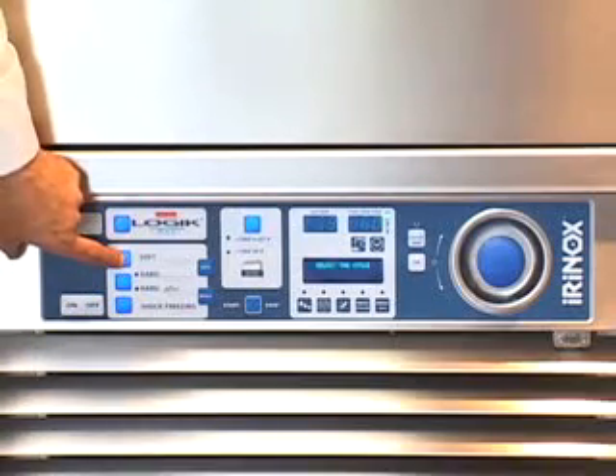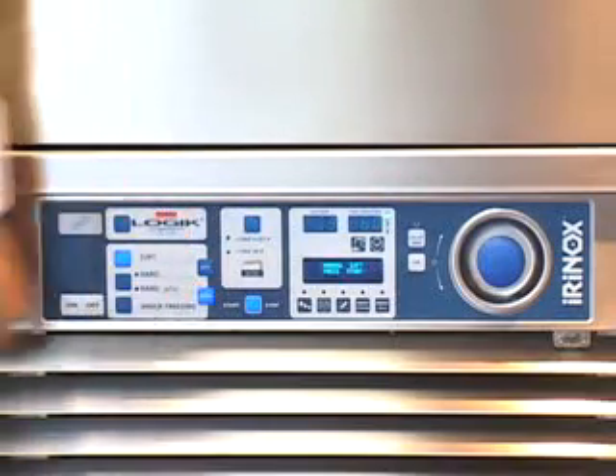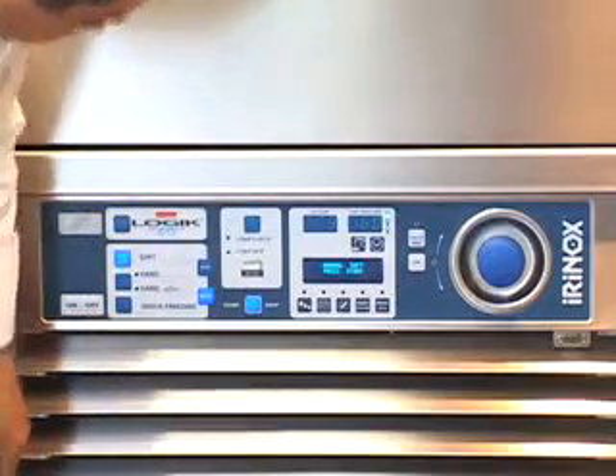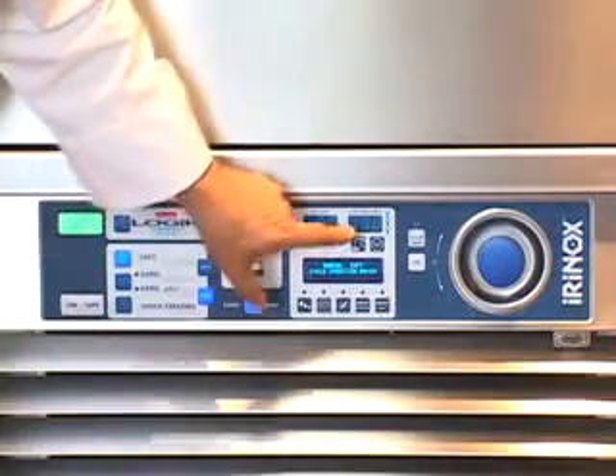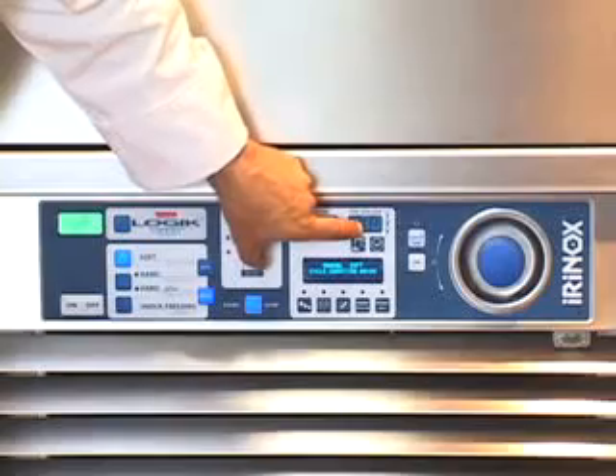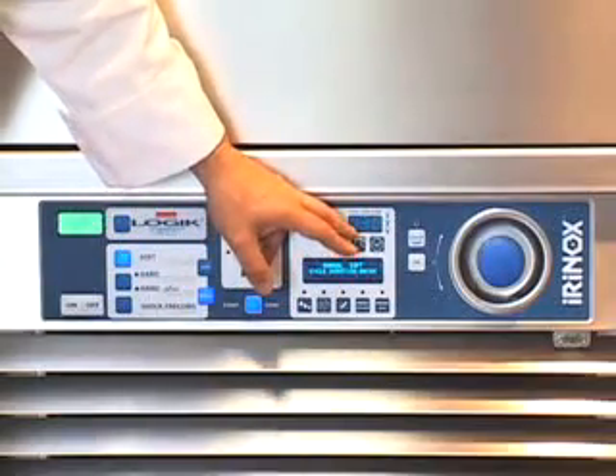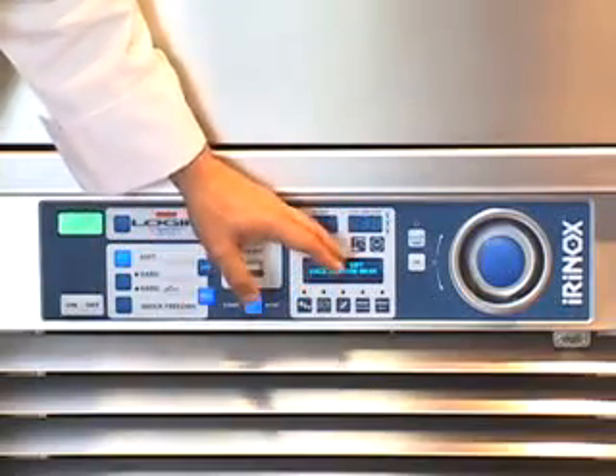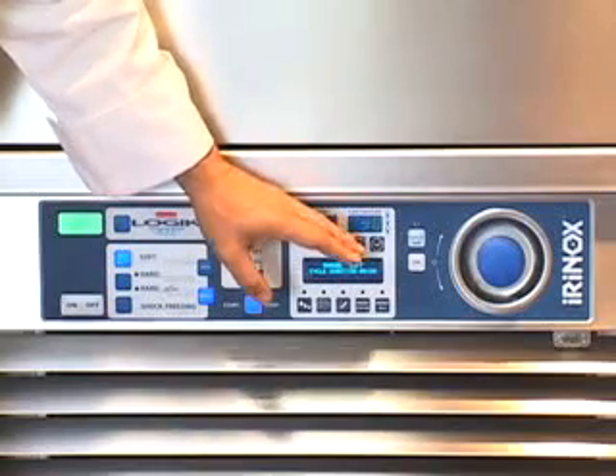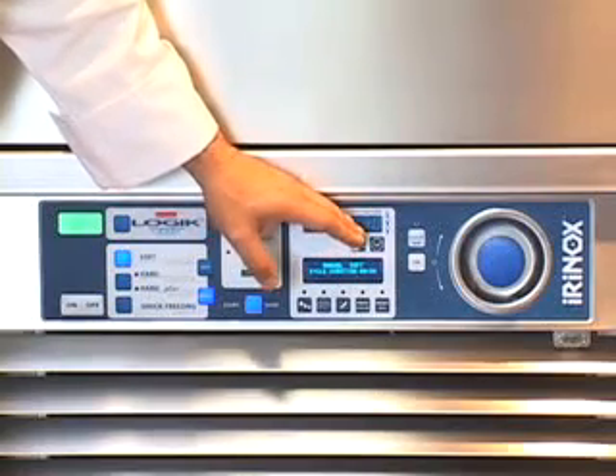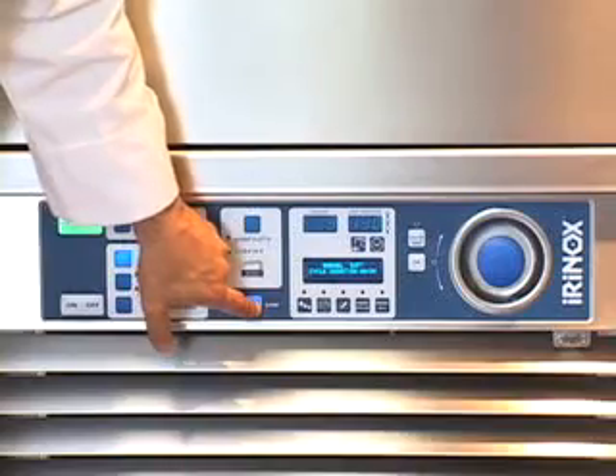So for example, if I hit the soft manual and I hit the start button, it's automatically going to show 1 hour and 30 minutes on the timer. It will run for 1 hour and 30 minutes in the soft chill mode, and then automatically at the end go into a holding mode until I hit the stop button.